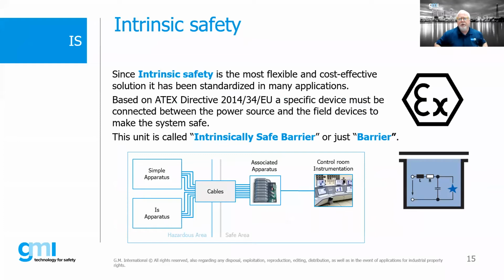So talking about intrinsic safety, it is one of the most flexible and cost-effective solutions, and it has been standardized for many different applications. I know many of you are located in various parts of the world. It is referenced within the IEC standards and the 60079 standards. There's two different standards on intrinsic safety within the 60079 series. One is, I think it's 11. I always get it mixed up. And the other one is 25. So those are the two standards on intrinsic safety. 11 is the standard that deals with how to build a barrier, so to speak, and 25 has to deal with the design of a system.